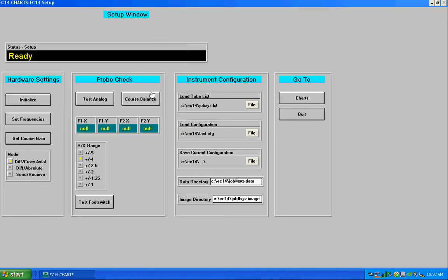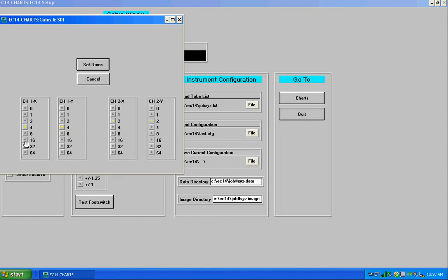Same thing with the course gain, this is a pre-amplifier gain, one of the gain stages. These have already been set by the last.config file so I'm not going to change those right now, but if you wanted to manually change those you can.